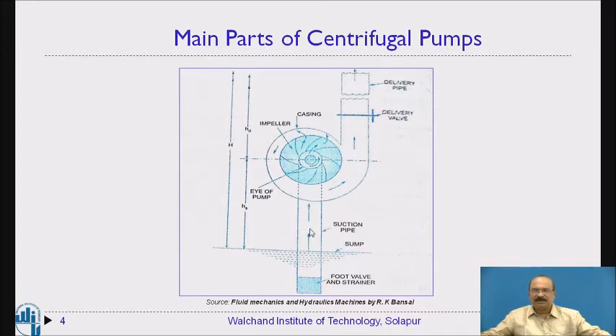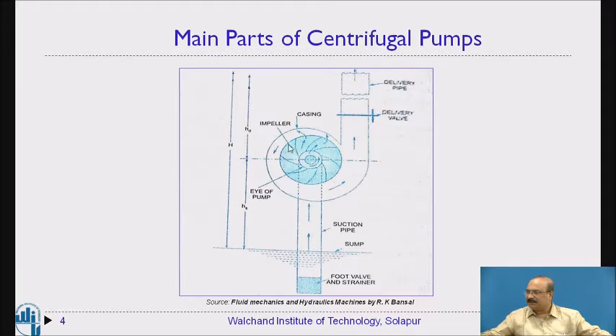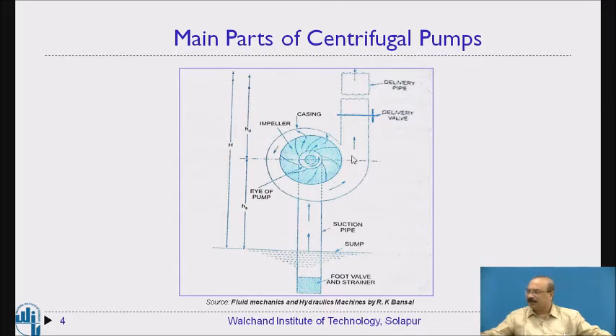In working condition, the centrifugal pump operates as follows. The shaft is connected to the motor; electrical energy is supplied to the motor and converted into mechanical energy. That mechanical energy is utilized by the shaft, which is connected to the impeller. The impeller has curved blades. When the shaft starts rotation, the impeller also starts rotating. Water is sucked through the suction pipe. Before starting the motor, we fill the complete pipe with water — that is, we remove the air inside the pipe. This is called priming of the pump.